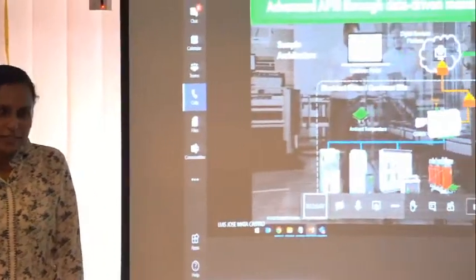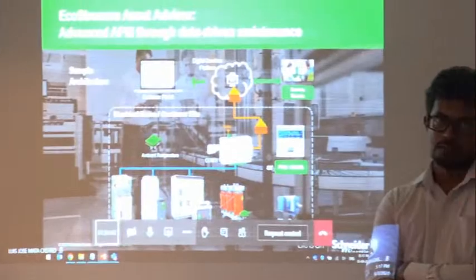Even with water meters and gas meters, which most of the time do not come with Modbus or BACnet but with M-Bus, a different protocol, we can convert it to Modbus and bring it into our system very easily without any disturbance. So this is actually possible.